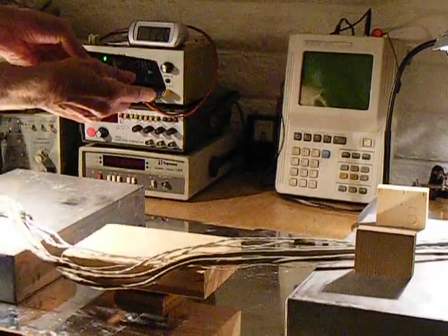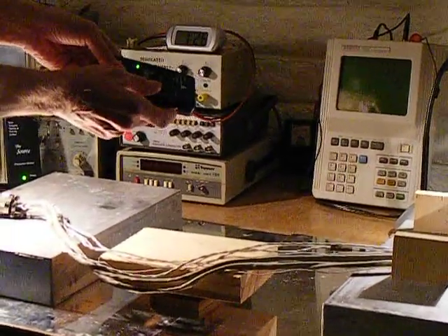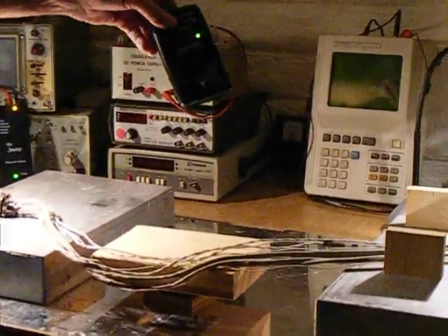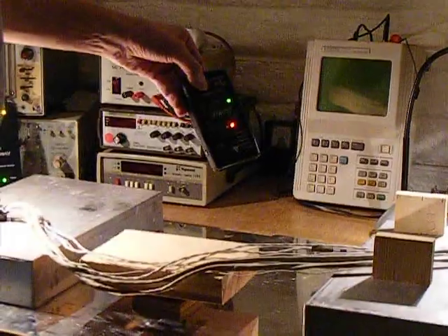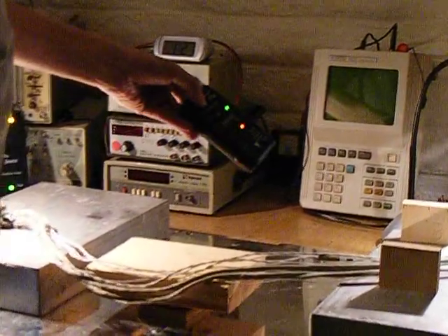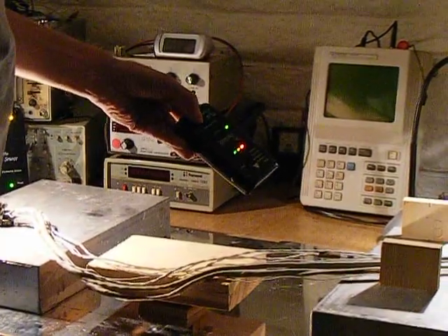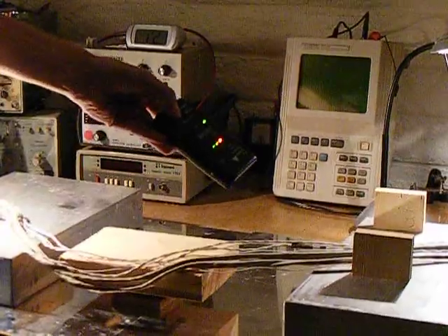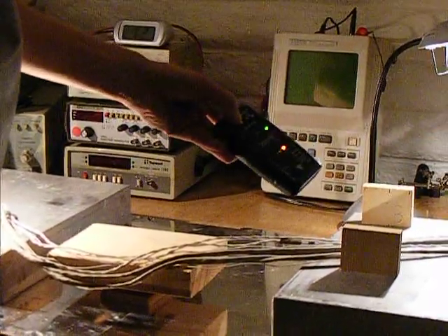To aid in that, without looking just in this area, although you could, let's turn this down and use our width to exactly locate where the wire is shorted. We'll turn it down, reducing its sensitivity so we can get closer to the wire. Again, we use the green LED as our indicator of signal strength. And there's our wire. Off the wire. On the wire. We can follow our wire's path.